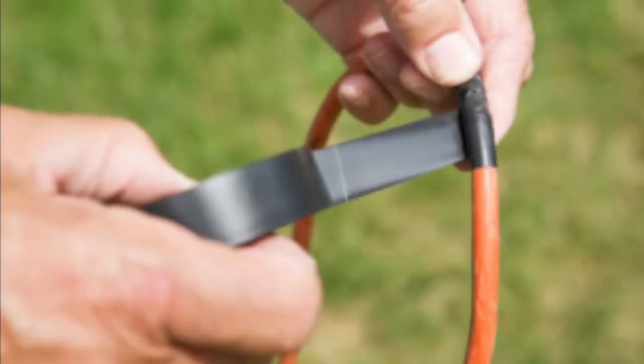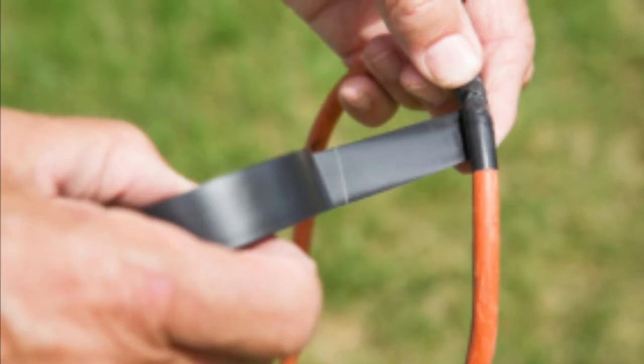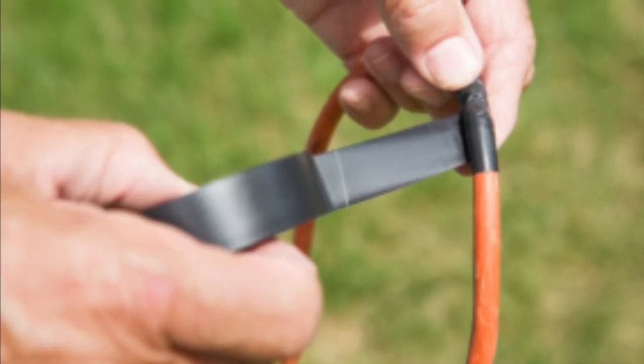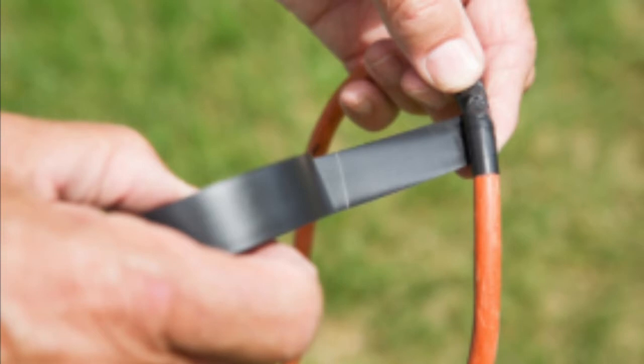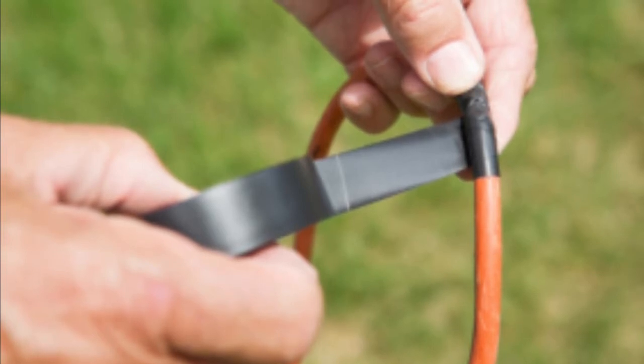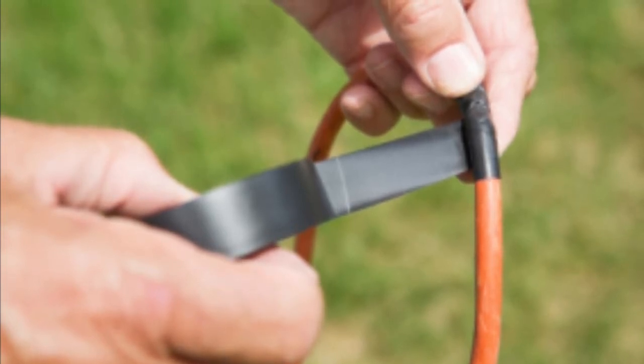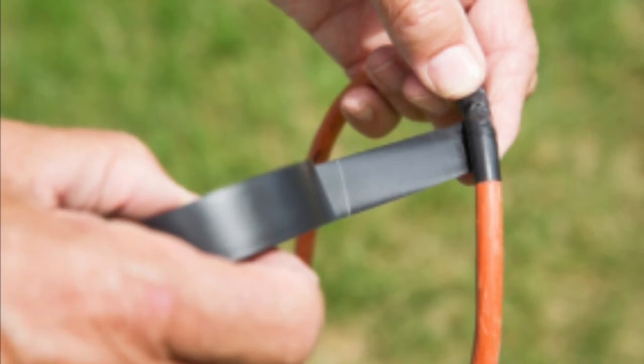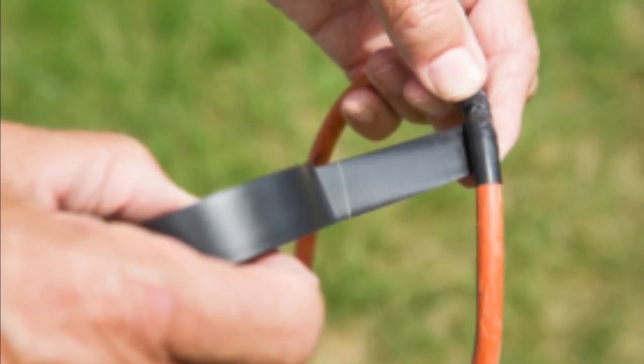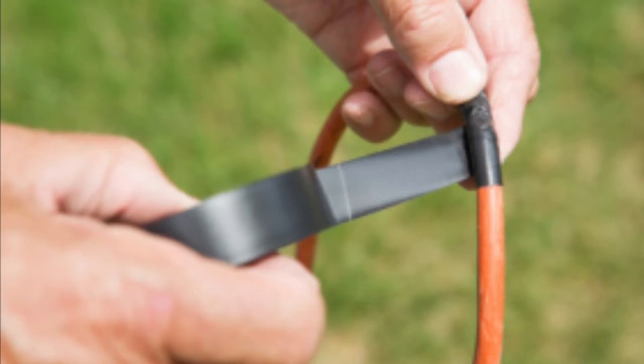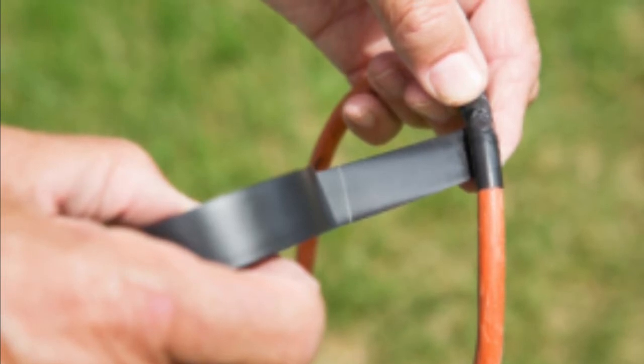OSHA allows the use of electrical tape to cover superficial damage to cord jackets. There is no prohibition against putting electrical tape over these kinds of abrasions and nicks when there is: 1. No damage beyond the jacket, 2. The conductors have not been scraped or exposed, and 3. The insulation inside the jacket has not been displaced or compressed.